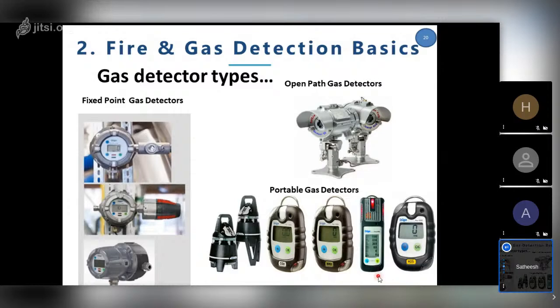Some are used for confined space monitoring checks. For example, before you enter that area, you want to ensure whether gas is there or not. And obviously we don't always have permanent gas detectors. So what you can do is, some devices come with a pump and you put in a hose. You switch on this equipment and put that hose in that area before you enter. Imagine a tank before you enter for cleaning, for example. You switch on this equipment and check whether there is gas present in that area or not. If there is gas present, you will get an alert so that you will not enter. So this is like an entry check. You can use it.